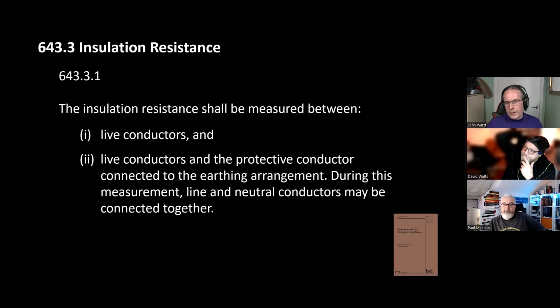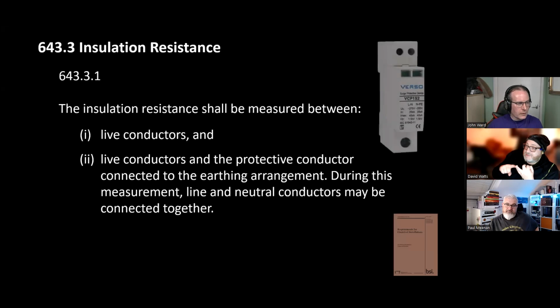And also, to be clear, 64 is initial verification, so this is your new installation that you've just installed. This is not periodic or EICR. I was taught that you always measure it before you connect all the accessories anyway, but it's fairly evident from these regulations that people are installing it, lashing it all together, second fixing it, then doing the IR test. You've got a team doing the cable pulling, a team doing the second fix, then another person, who may be the one verified by the CPS, coming at the very end doing the initial verification. Just remember, guys and girls, when you are doing it, remove the surge protection device.